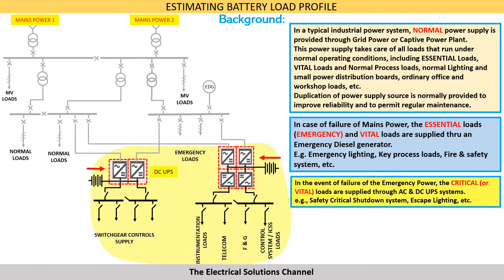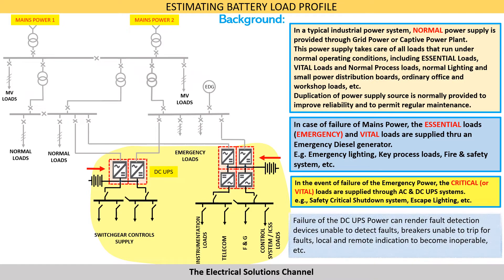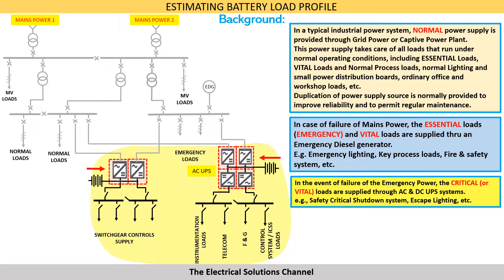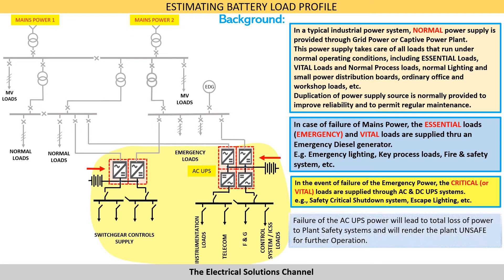Failure of DC UPS power can result in fault detection devices being unable to detect faults, breakers unable to trip on faults, and local and remote indication becoming inoperable. Failure of AC UPS power will lead to total loss of power to the plant safety systems and will render the plant unsafe for further operation.